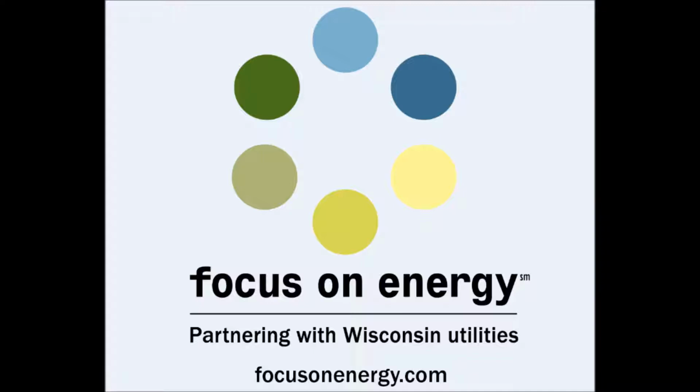And then lastly, I just wanted to touch on replacing bulbs, especially if you have linear fluorescent bulbs in maybe a shop or freestall, to save some labor and also to save a little bit of maintenance and time. We would really recommend replacing all of your lamps at one time, relamping and reballasting at the same time. And it's been recommended in the past to do that every 3 to 5 years. With that being done, you're replacing them all at once. Then you're not just replacing per burnt out bulb, because typically when a few start burning out, you'll see more and more coming in the future.